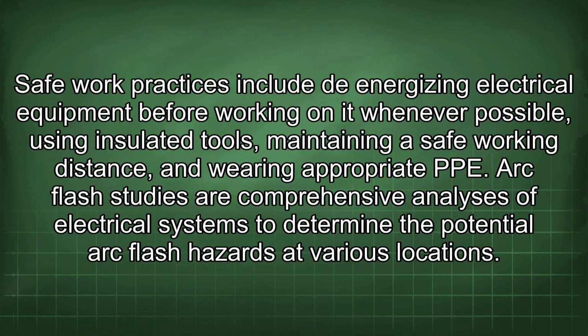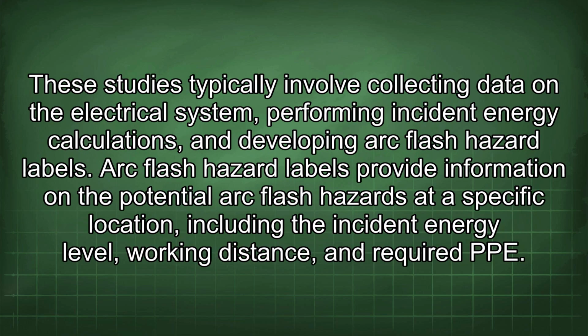Safe work practices include de-energizing electrical equipment before working on it wherever possible, using insulated tools, maintaining a safe working distance, and wearing appropriate PPE. Arc flash studies are comprehensive analyses of electrical systems to determine the potential arc flash hazards at various locations. These studies typically involve collecting data on the electrical system, performing incident energy calculations, and developing arc flash hazard labels.